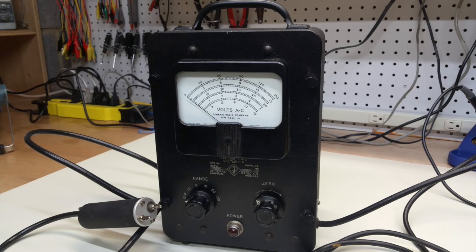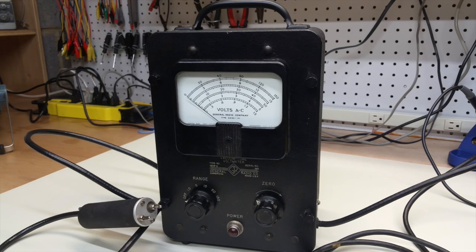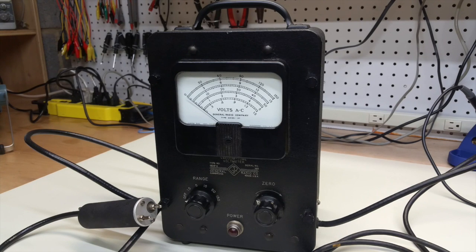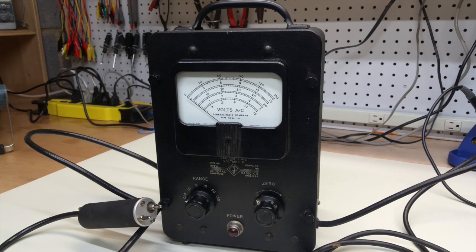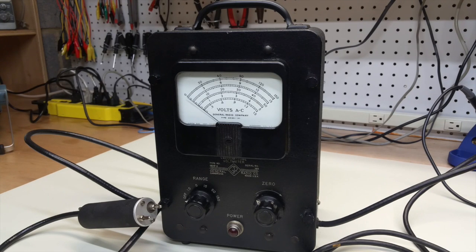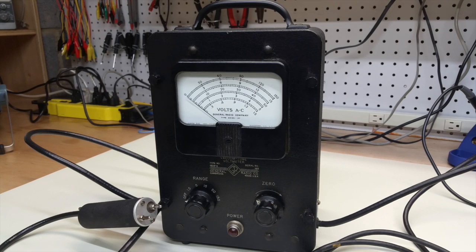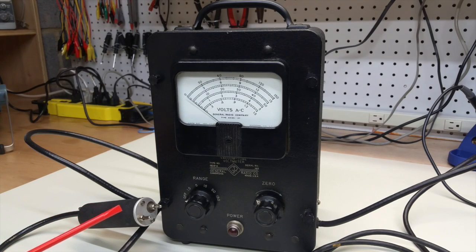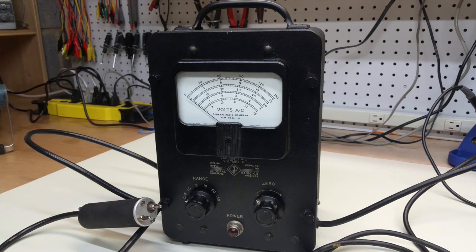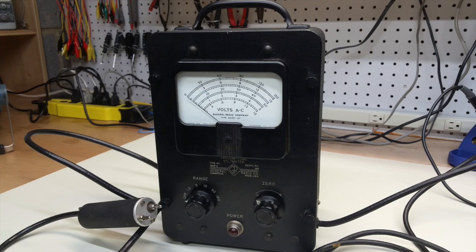It measures 0 to 150 volts AC in five scales. And one of the interesting things about this unit is that it can measure AC that has frequency up to about 120 megahertz.